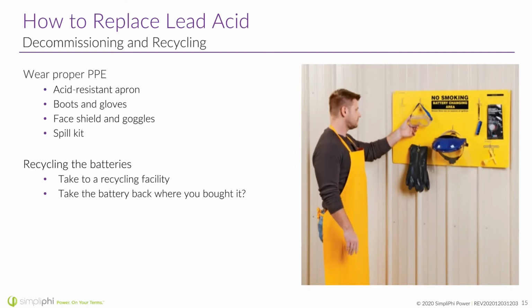Moving on to the actual replacement process, make sure to decommission and recycle your lead acid batteries properly. This means wearing proper PPE, such as an acid-resistant apron, boots, gloves, everything made of rubber, a face shield, and a spill kit. I remember helping remove some lead acid batteries from a customer's home. They were still connected and basically sizzling and popping and leaking electrolyte everywhere, so we had to go in full PPE to take care of them—long sleeves, long pants for sure.